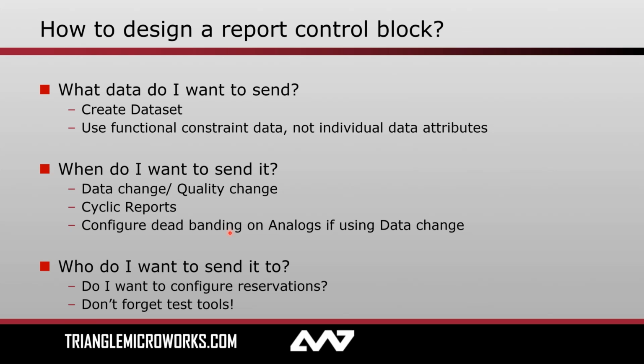And then finally, you have to decide, who do I actually want to send my data to? Do I want to configure reservations? Who should those reservations be for? And then finally, don't forget about test tools. Please, as someone who works daily with a variety of 61850 test tools, when you're designing reports, design some extra ones in there. Think about not just what information I want for my SCADA system, for my historian, for alarms. Excuse me, what information do I want to be able to pass to a test tool, maybe during commissioning or troubleshooting that might happen down the line.